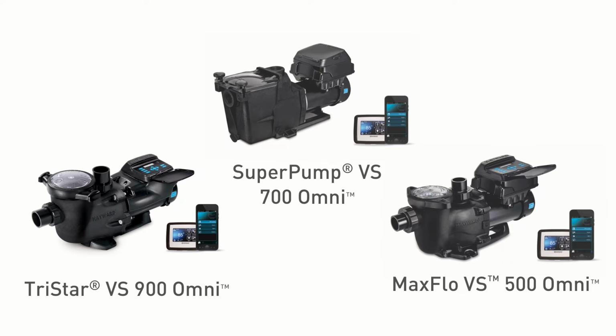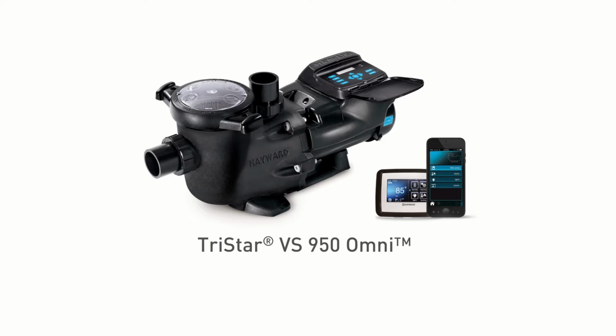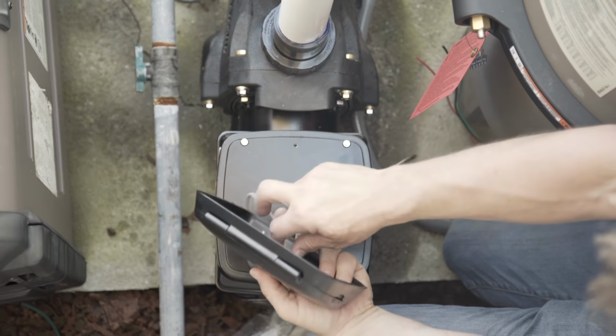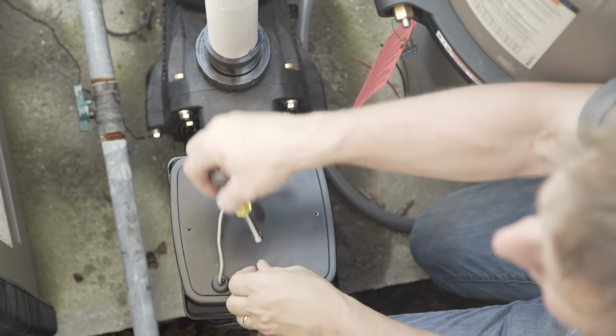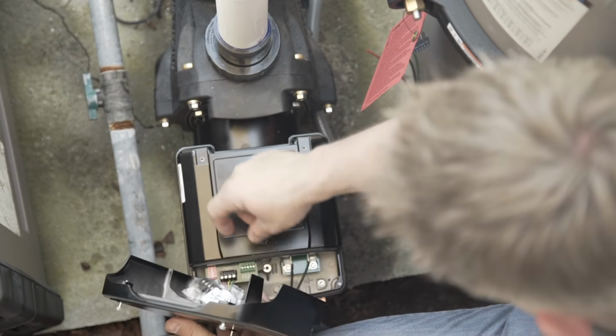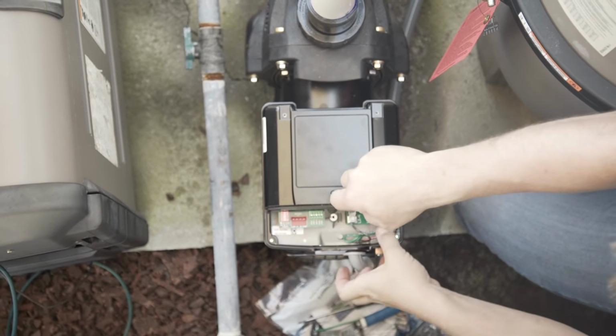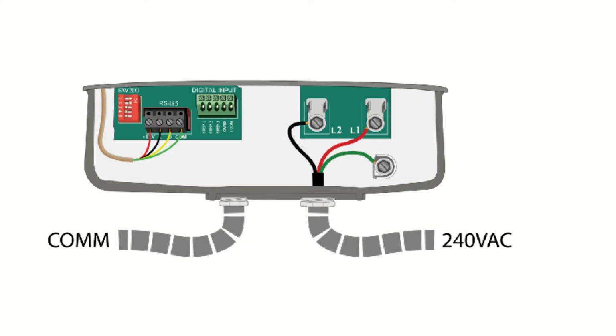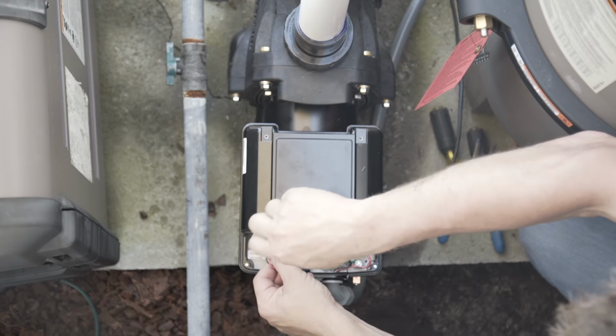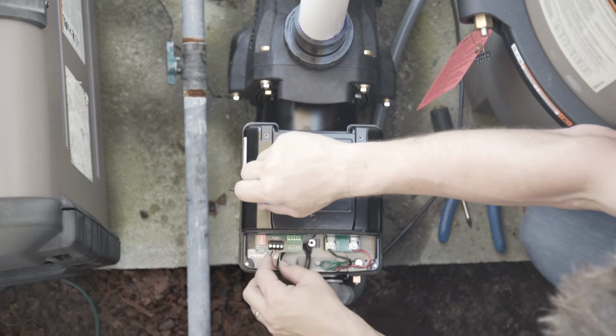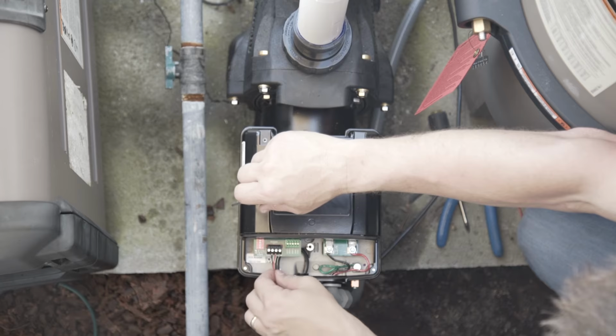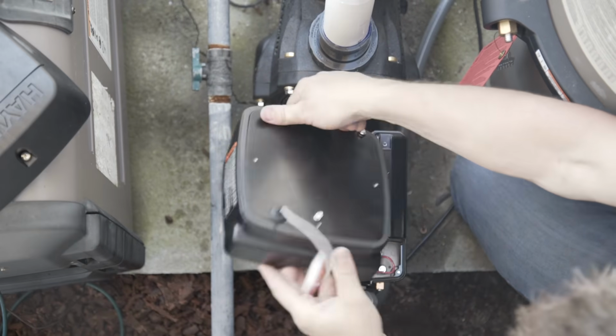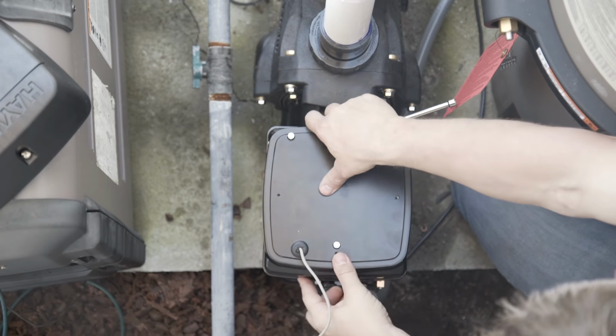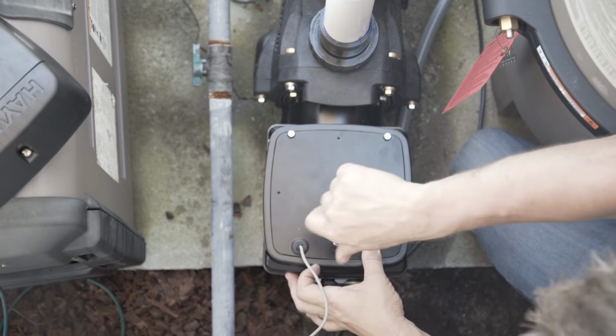The following instructions are for the TriStar VS900 Omni, Super Pump VS700 Omni, and MaxFlo VS500 Omni only. We will cover the TriStar VS950 Omni later in this video. Unthread the screw, remove the cover plate, and reveal the variable speed pump's wiring compartment. Wire the high voltage wires to L1 and L2 as shown. Also connect the ground wire. Next, disconnect the 4 wires going to the RS485 connector. Cap or tape these wires inside the wiring compartment. These wires should only be reconnected if the pump needs to be run in standalone mode. For example, if the wiring hub or touchscreen display is being serviced.